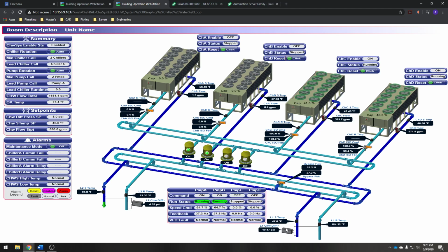And there are 2 loops. We do know the differential pressure, that's for redundancy. If this sensor dies, we don't want the system to freak out and either shut off or run at 100%. Best case scenario, everything runs at 100%, but that's not always the case. We've had data center outages over less in various sites that we own. So that's why we have 2. It'll always control off the one that's lower, closer to the set point, is how it's set up.